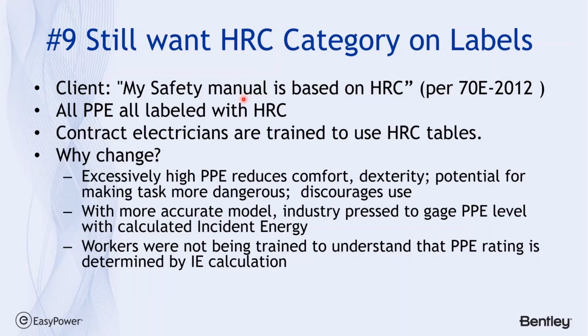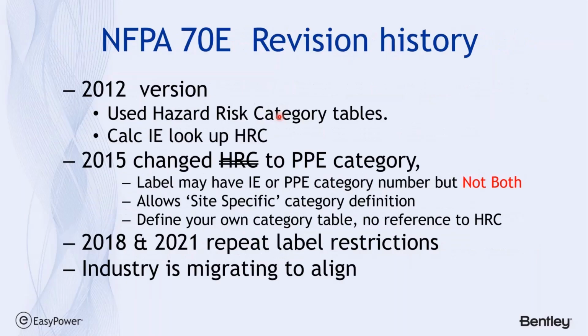Well, you can quote to them per 70E, starting in 2012, that PPE labels can't have both the incident energy and the lookup PPE value from the standard. Now, in 2015 they took off the reference to HRC, which is hazard risk category, and they changed the tables' name to PPE category, but still they say a label may not have both the incident energy and the category number for PPE.